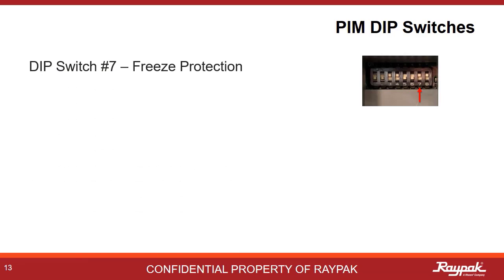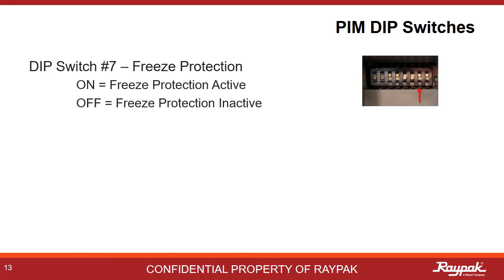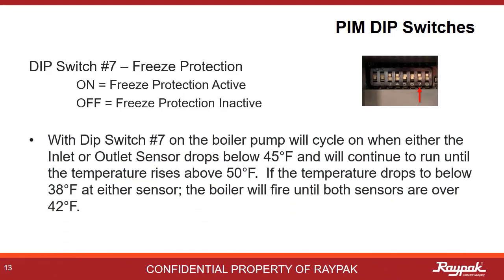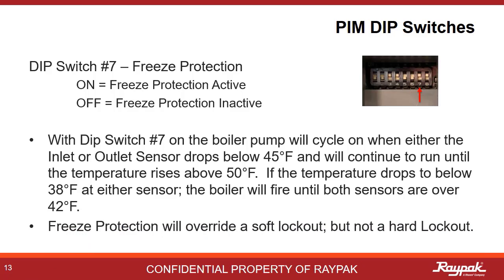Dip switch number seven is another example of some cool Raypak engineering. Turning on number seven enables freeze protection for the boiler. If the temperature drops below 45 degrees at either the inlet or the outlet sensor, then the boiler pump will fire for a bit, drawing some heat from other areas in the system, until the temperature is higher than 50 degrees at both sensors. If the temperature continues to drop and gets below 38 degrees at either sensor, then the boiler will fire for a few minutes until both sensors are over 42 degrees Fahrenheit. This process will override a soft lockout, but not a hard lockout, as that could be dangerous.